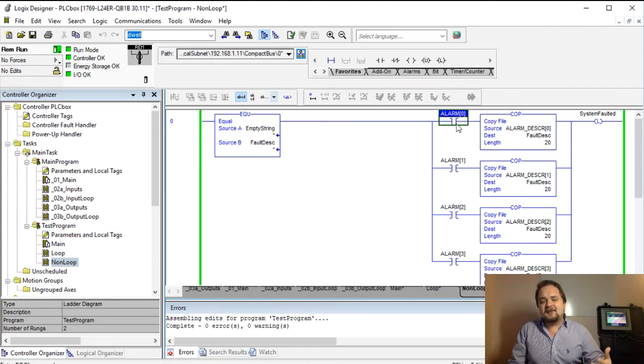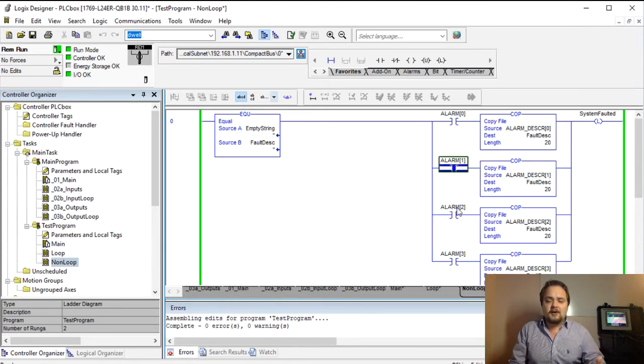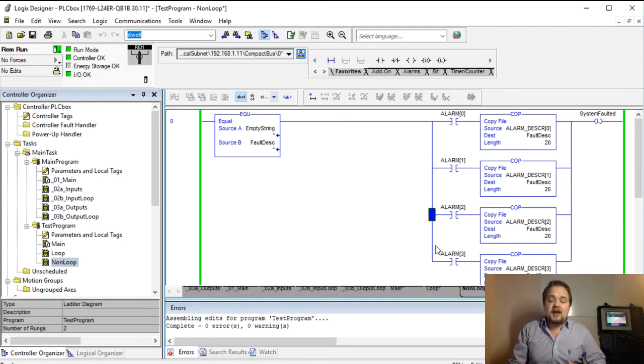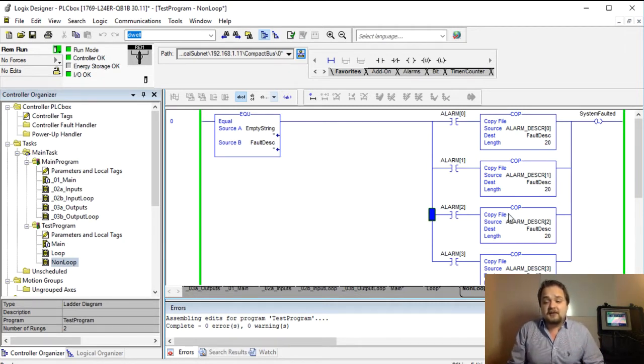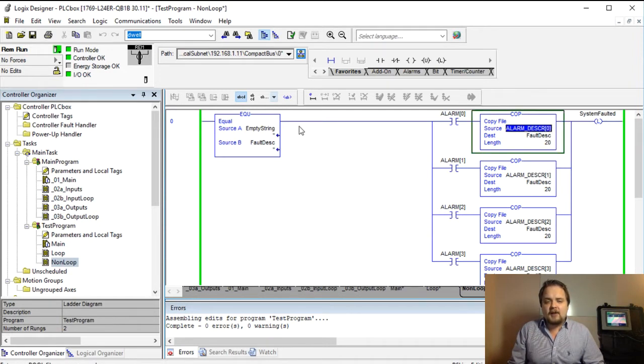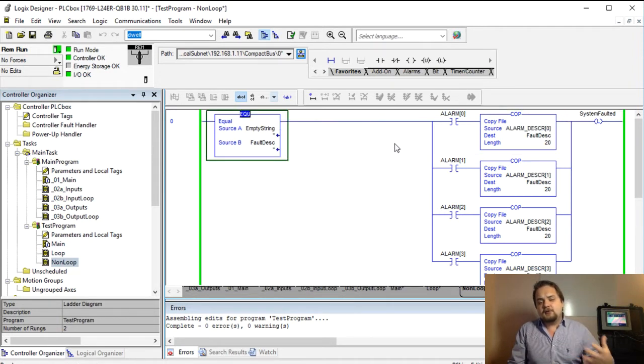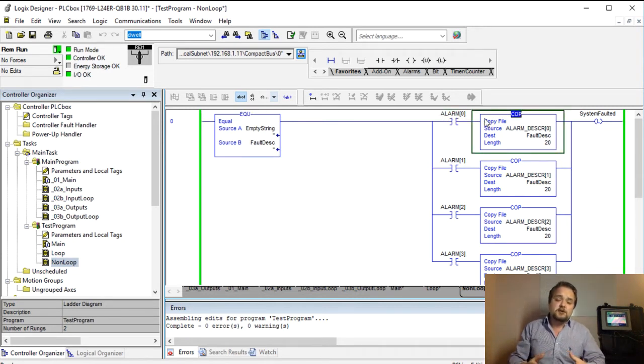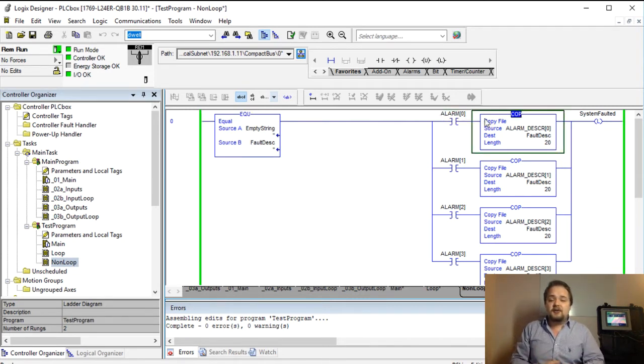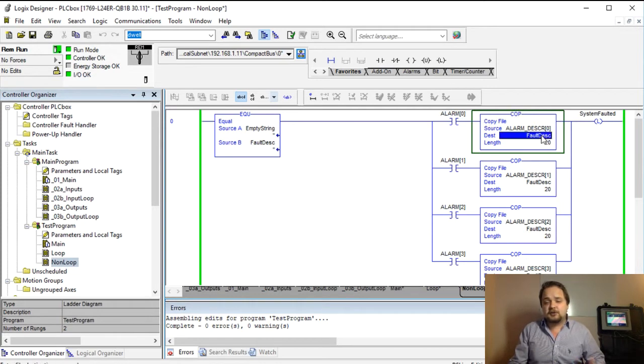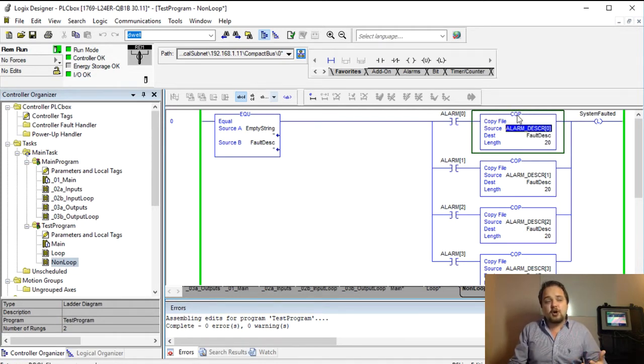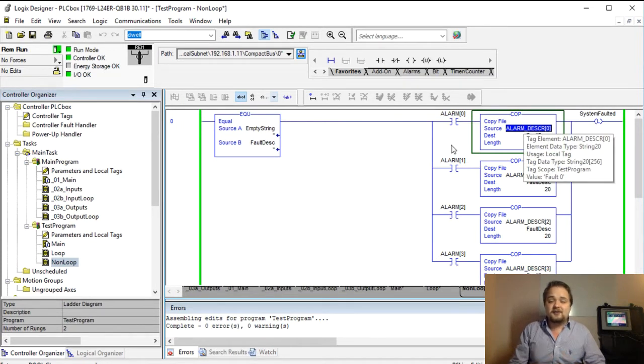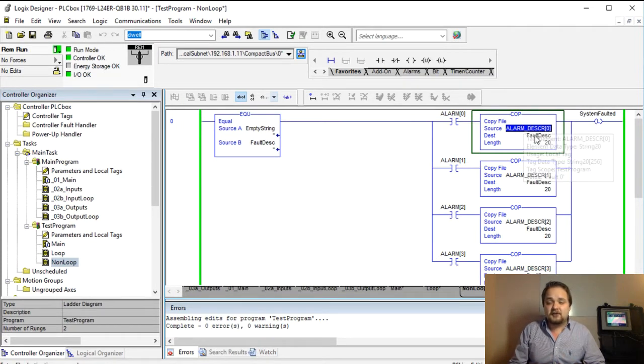So you have alarm 0, 1, 2, 3 and I've essentially not implemented all of them but you could have as many as thousands of alarms that I've seen in a normal scenario and what happens here is so when you have no fault and a certain fault occurs, you want to capture the description of that particular fault within your fault description string. So what you're doing is you're copying the alarm definition for that particular alarm into that fault description.